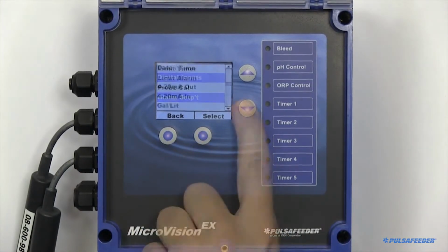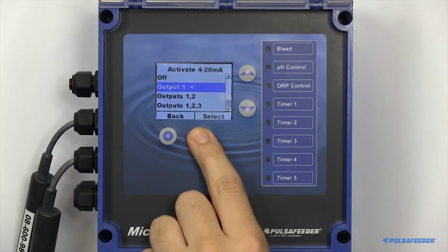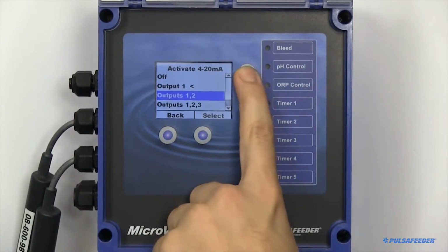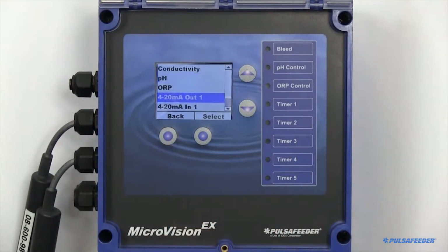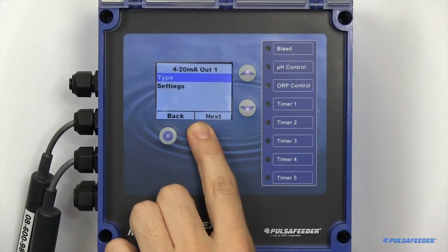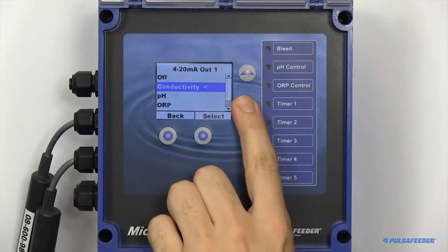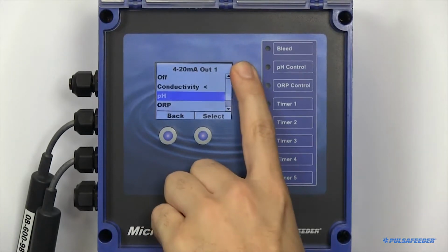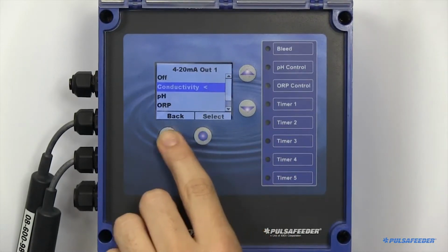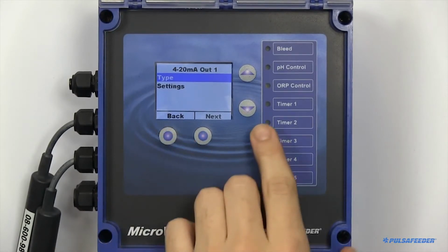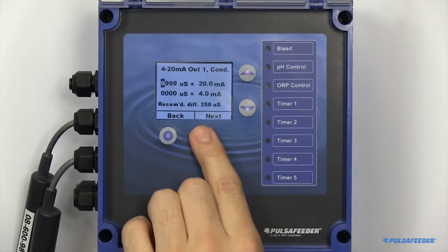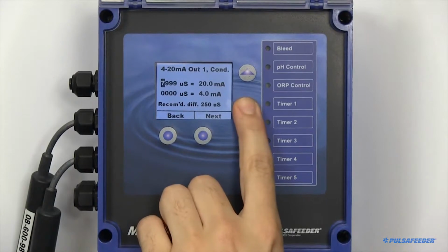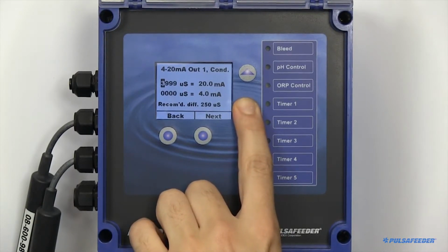If you have a 4 to 20 output board, this can also be configured here. First, make sure it is enabled from the configure menu. To set up a 4 to 20 output board, you will first need to configure the type. After setting the type, go to the settings page. This is where you will scale the reading. Here you can tie the actual probe reading to a milliamp value.